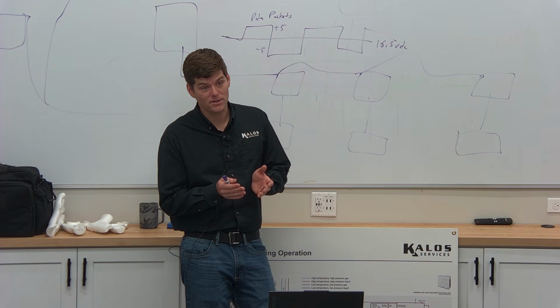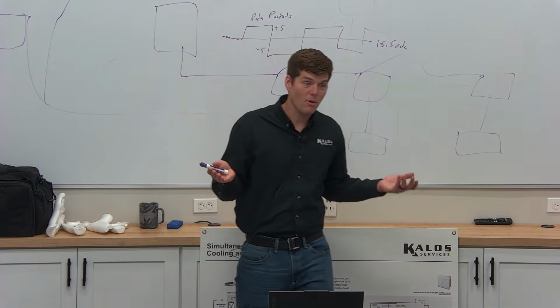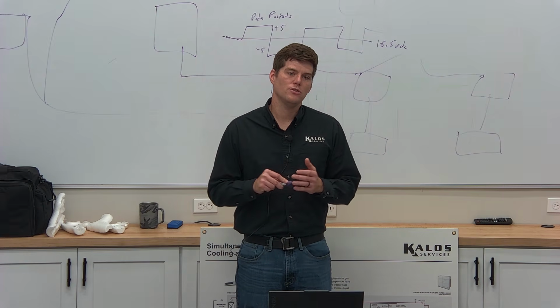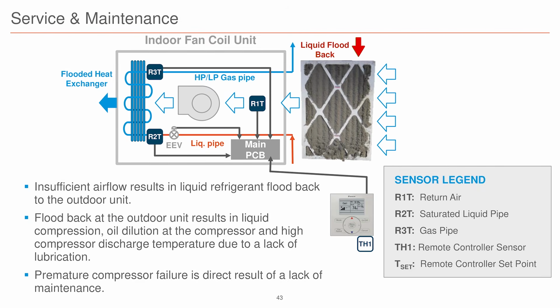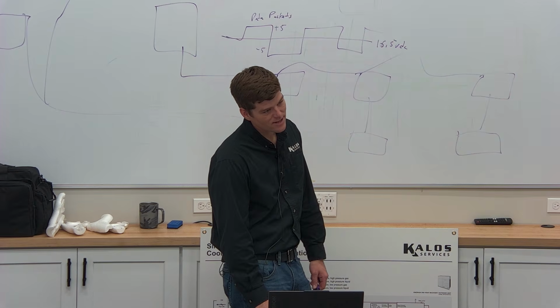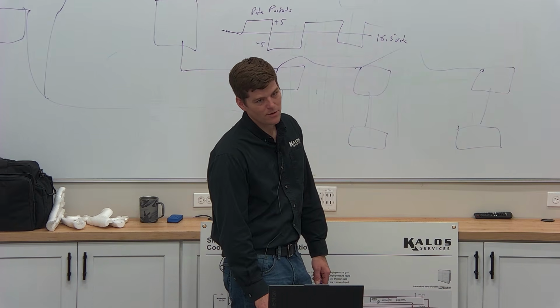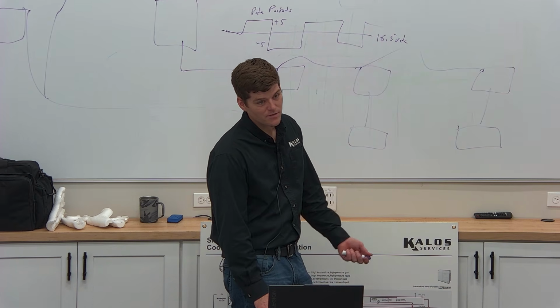I'm getting liquid in my suction line, which is not something we want. So just be mindful. All of these units are using the same exact thing. Just a quick display, right? Why would I have a low superheat on an indoor fan coil? Dirty filter, right? Lack of airflow. It's a heat exchanger, guys. It's designed to exchange heat. What's one thing that would affect a heat exchanger? Insufficient airflow. This is all the fun service data you get to look at.